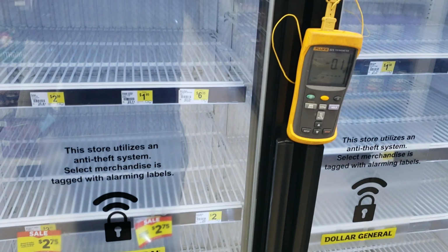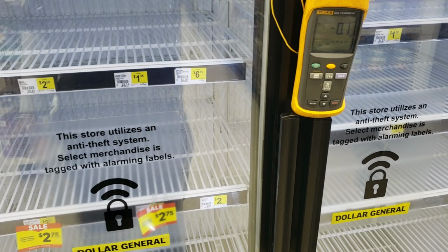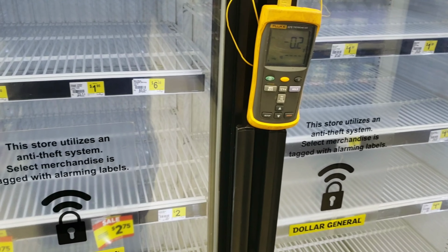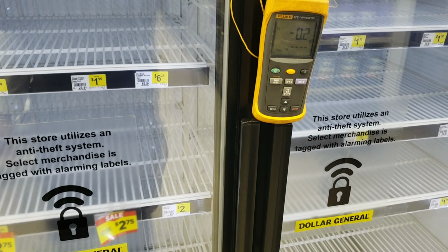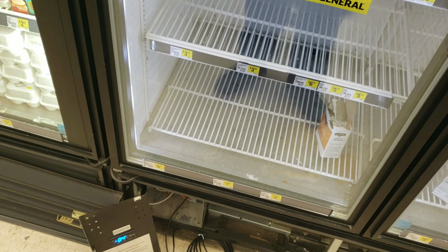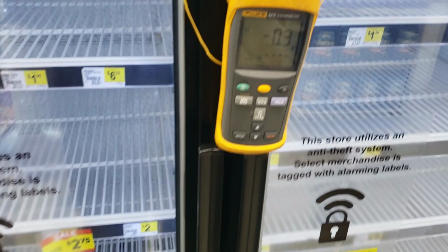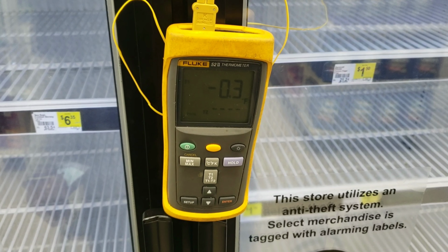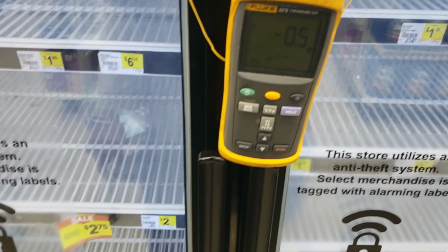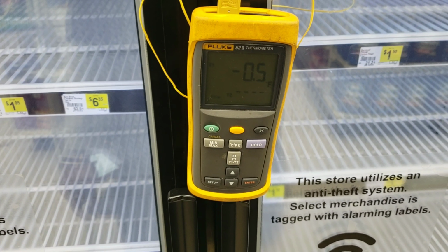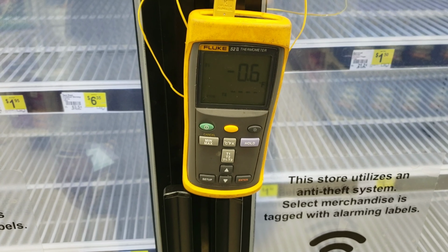We're gonna keep monitoring this system. Don't slap these modules on and hop in the truck and roll out, because you really need to verify. We've already cleared one defrost cycle. I'm gonna let this thing cycle a couple of times, because these modules come pre-programmed from the factory. You're not adjusting the defrost cycles or the length, so you want to make sure that they programmed all of this stuff correctly.